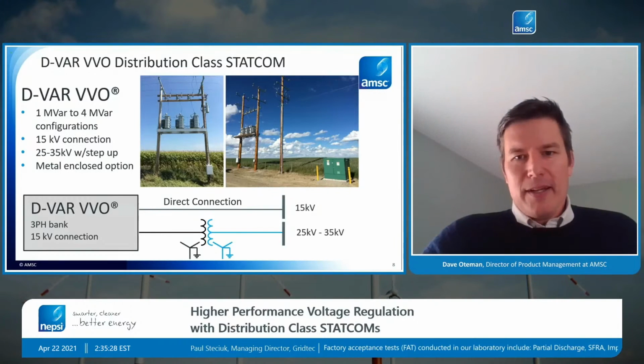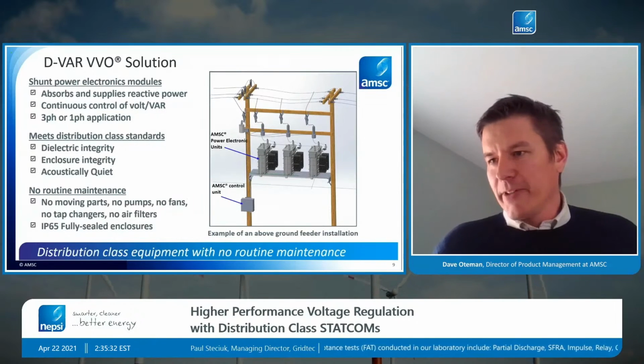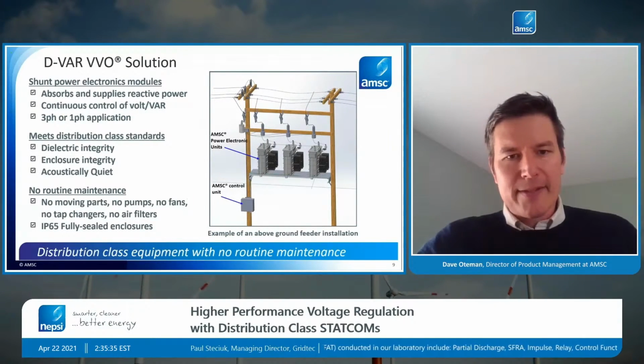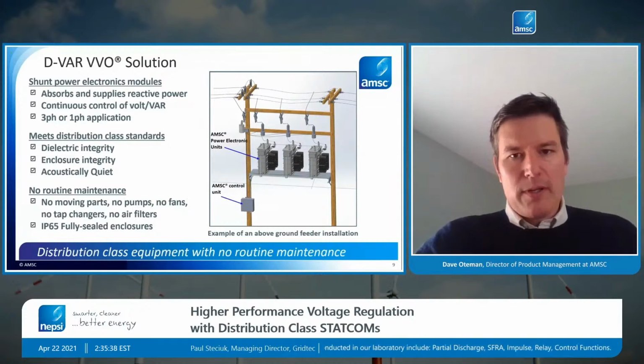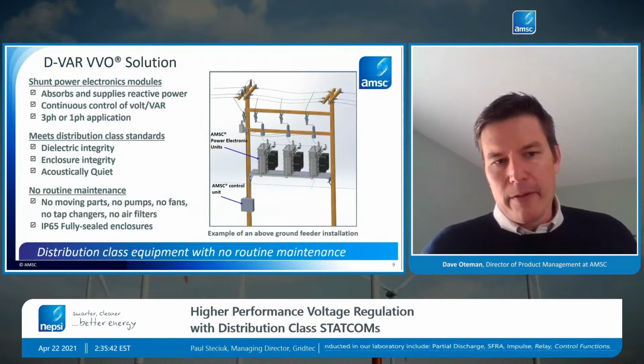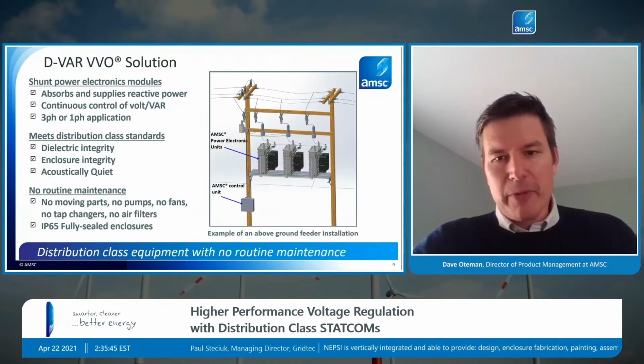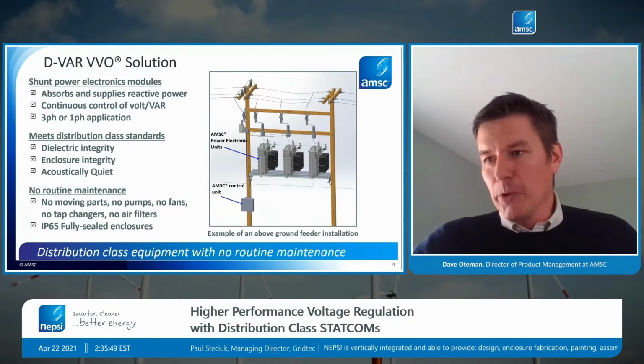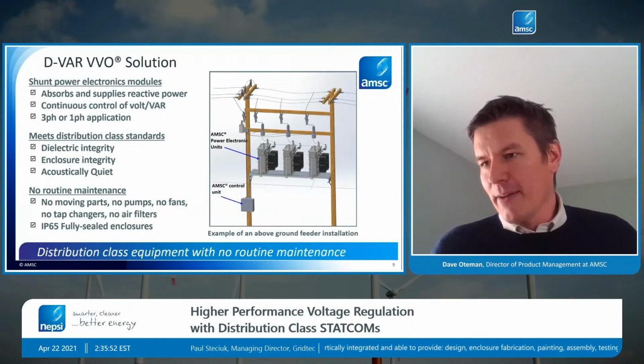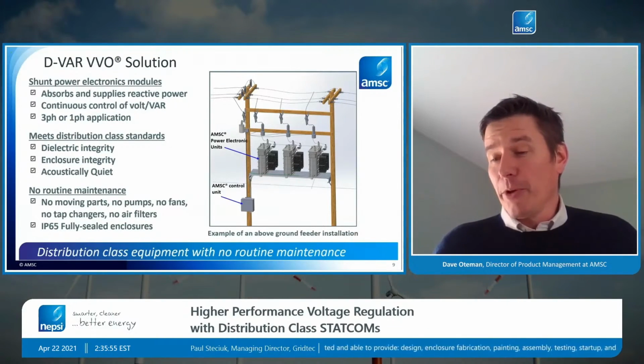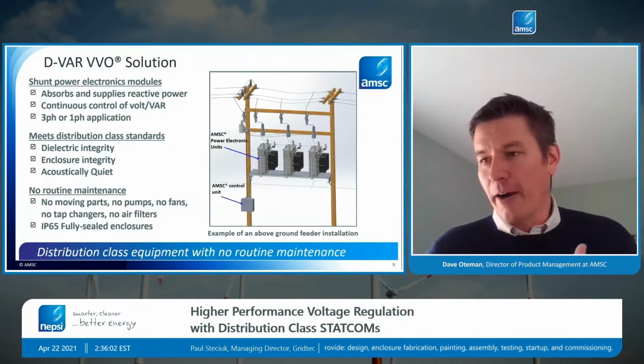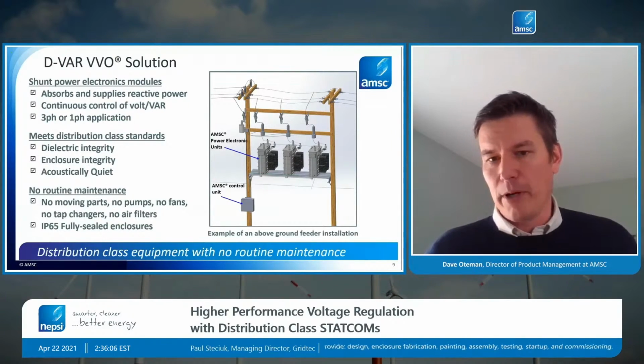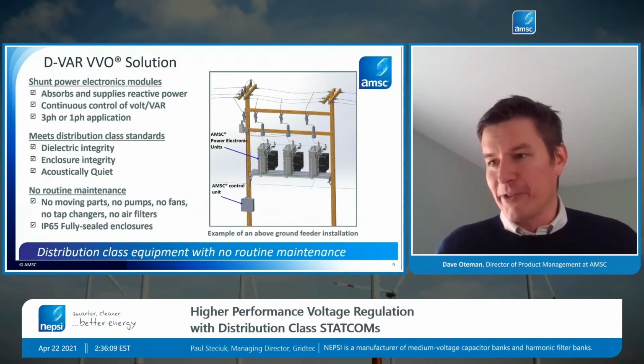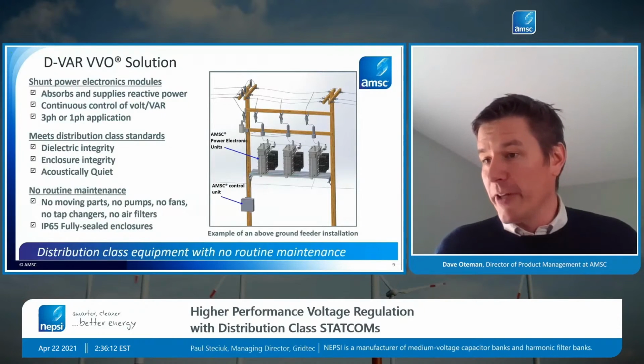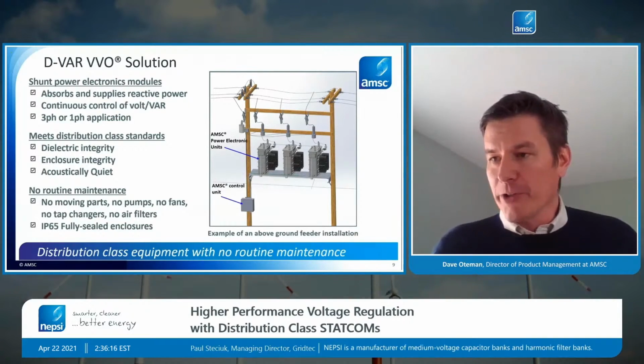Great questions, Paul. So we saw the actual installations. What I want to point out on this slide is really the no routine maintenance achievement we've accomplished with this solution. You'll notice radiators on each of these power electronic units. The cooling principle is quite similar to that used in a modern distribution transformer, so there are literally no moving parts: no fans, no pumps, no air filters to change out, and no coolant fluid that needs to be managed as in a forced cooling system.